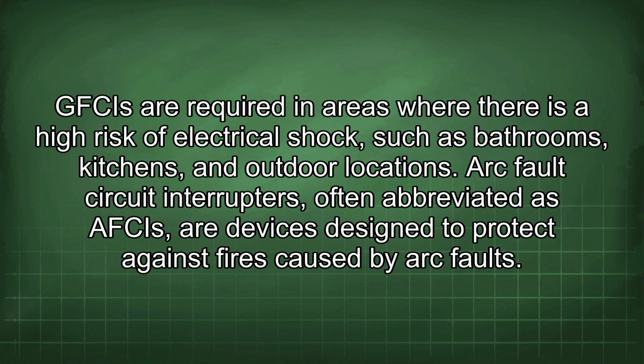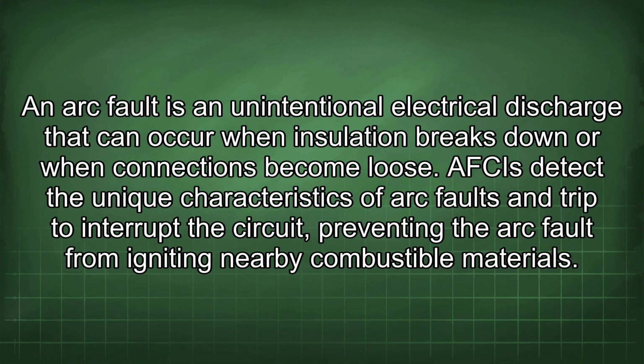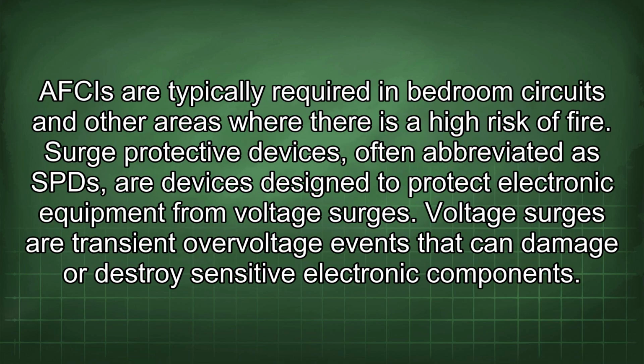Arc fault circuit interrupters, often abbreviated as AFCIs, are devices designed to protect against fires caused by arc faults. An arc fault is an unintentional electrical discharge that can occur when insulation breaks down or when connections become loose. AFCIs detect the unique characteristics of arc faults and trip to interrupt the circuit, preventing the arc fault from igniting nearby combustible materials. AFCIs are typically required in bedroom circuits and other areas where there is a high risk of fire.